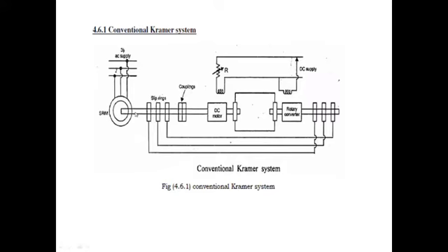When rotor copper loss is neglected, PR is equal to the slip power in the slip power recovery scheme of an induction motor. Speed control below synchronous speed is obtained by controlling the slip power. The same approach was adopted in rotor resistance control. However, instead of wasting power in an external resistor, it is utilized here. Therefore, these methods of speed control are classified as slip power recovery schemes. It provides the speed control of a slip ring motor below synchronous speed.